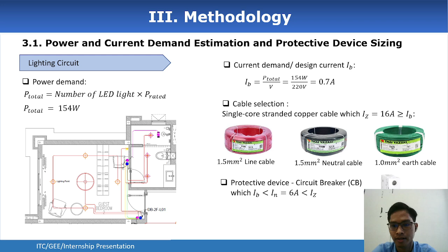For the socket outlet circuit, we do the same, but we know that the current rating of a power socket is 16 amps per socket. So the power rated by a socket is 220 volts times 16 equals 3.52 kilowatts. For the cable selection, we do the same as for the lighting circuit.